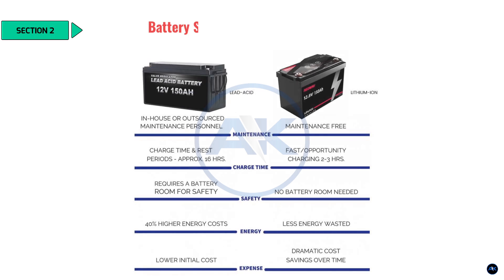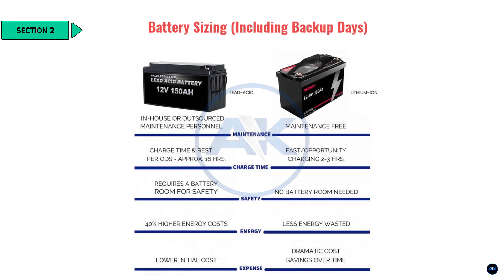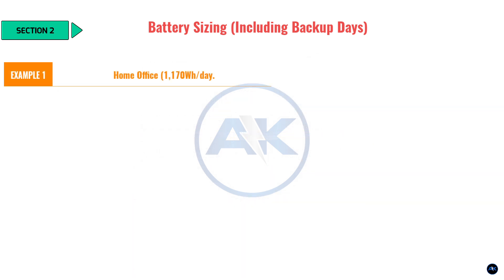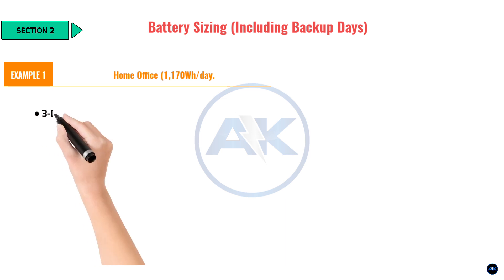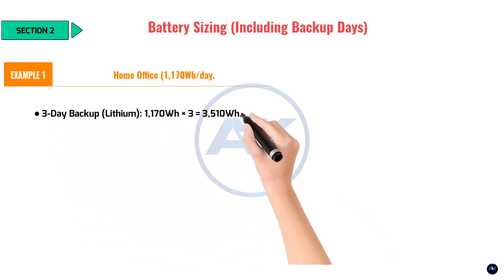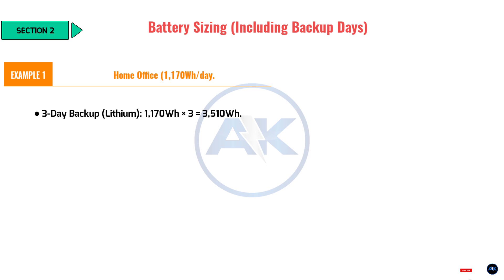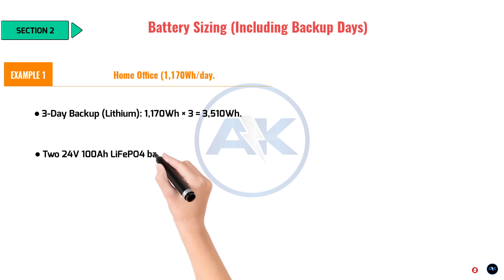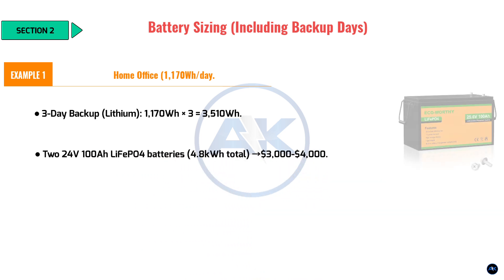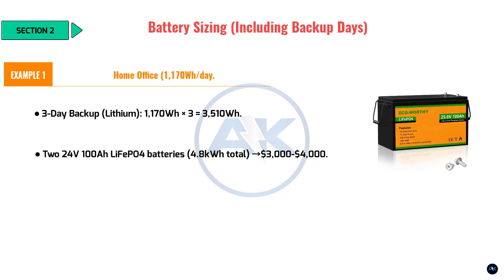Section 2: Battery sizing, including backup days. Now let's size your battery. Do you want backup power for cloudy days? A good rule is 3 to 5 days of autonomy. Example 1: Home office load — 1,170 watt-hours per day, 3-day backup, lithium. 1,170 Wh × 3 = 3,510 watt-hours. Two 24V 100Ah lithium iron phosphate batteries = 4.8 kWh total, costing $3,000–$4,000.